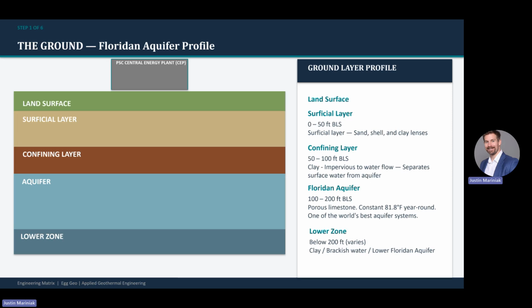So how is a geothermal system constructed? We need to look at the ground in our area. First, we have the land surface. Below that, the surficial layer, which is 50 feet deep and composed mainly of sand and shell. Next is the confining layer, which is made of clay and separates the surficial layer from the aquifer itself. It helps keep the aquifer relatively clean and protected. There are several layers below that, including other confining layers and other aquifers, some with saltier water.